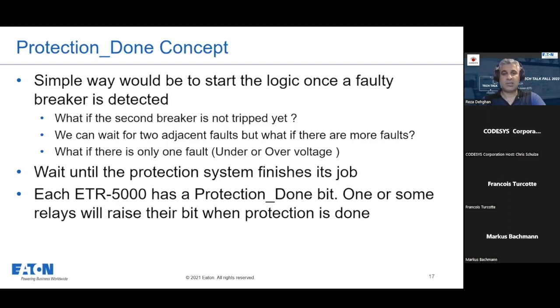And each ETR 5000 has a protection done bit. One or some relays will raise their bit when the protection is done. So as long as we see one protection done bit in the system, we know that everything is done. Protection has isolated the fault, and now it's time for the SMP gateway to start its logic. Next page.